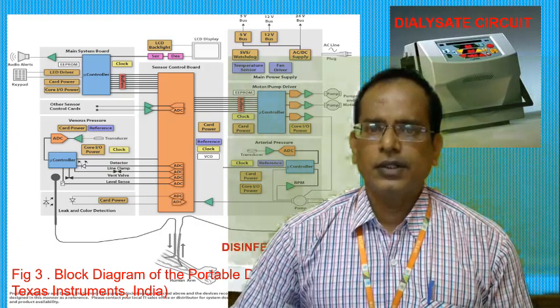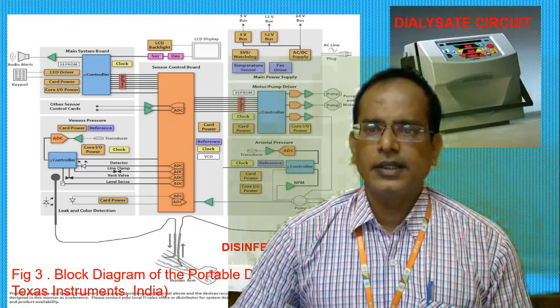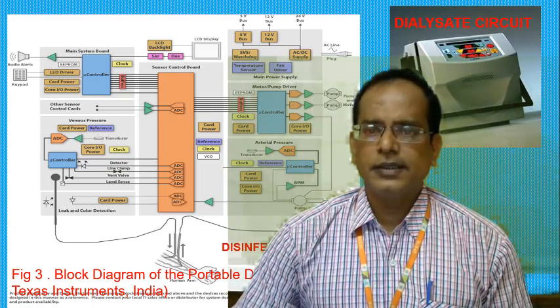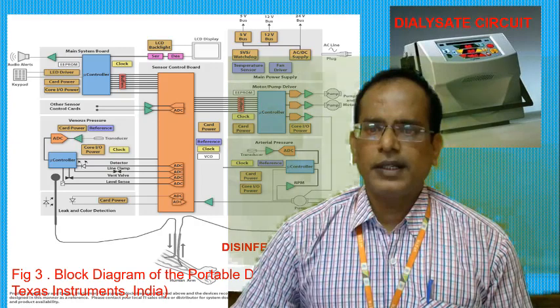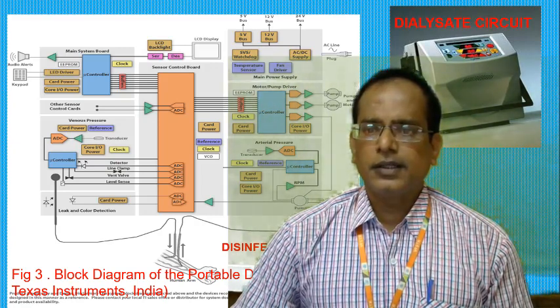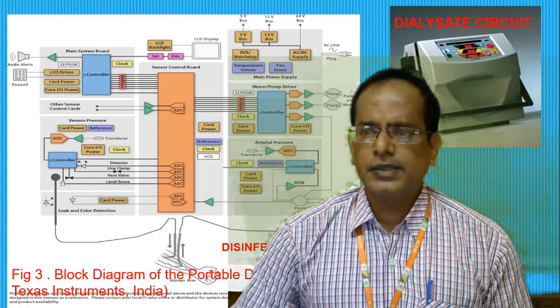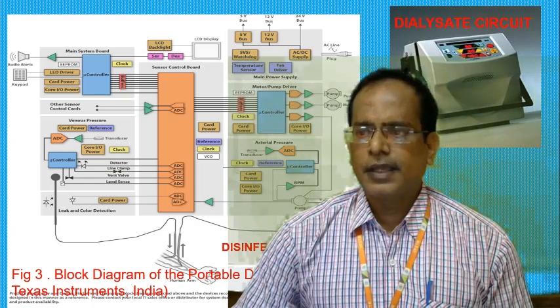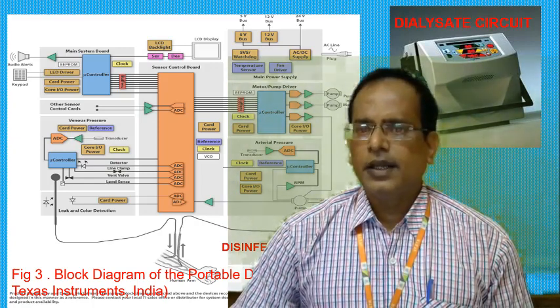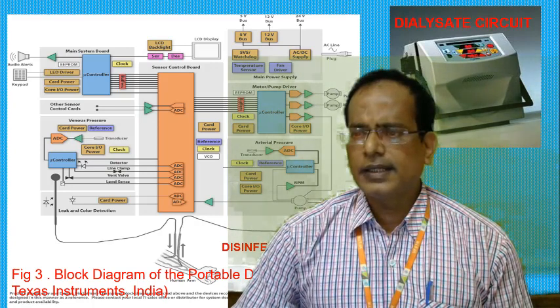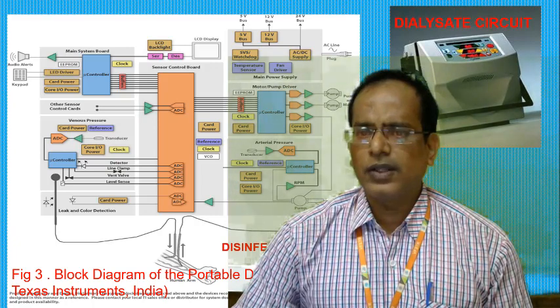Next is the disinfection circuit, which is another part of the portable dialyser. After the dialysis process is complete, the machine must be cleaned and sterilized. Provisions are made in the plumbing to close the circuit into a loop and run saline and sterilized water through the system to flush away all impurities.